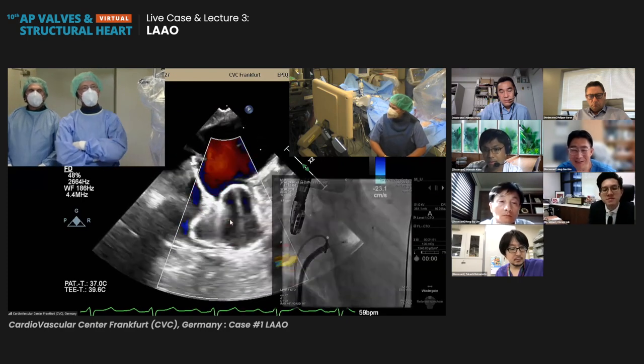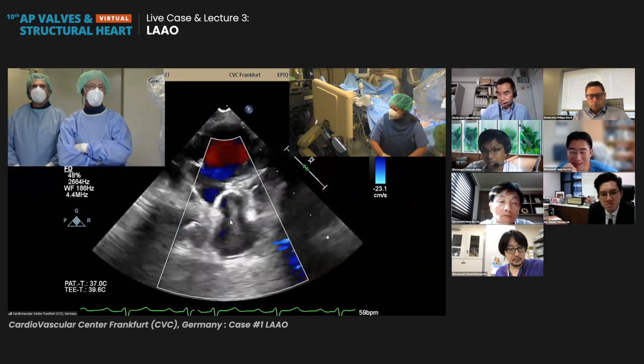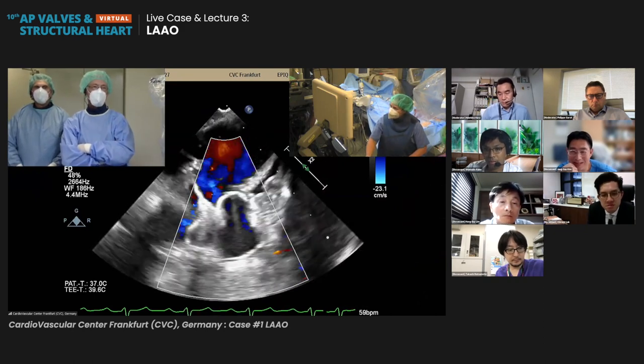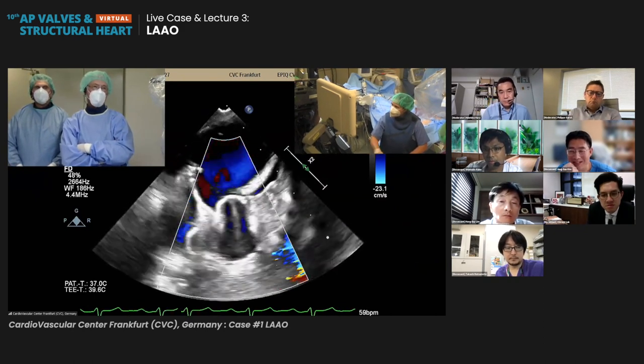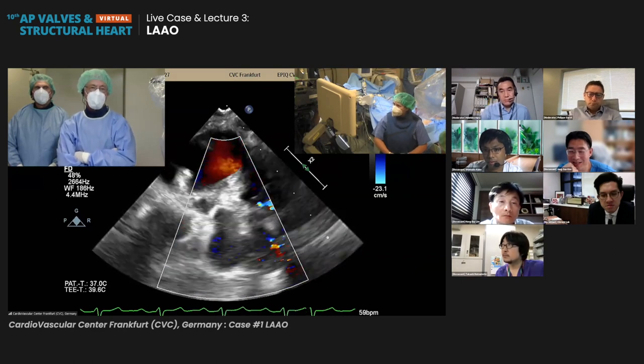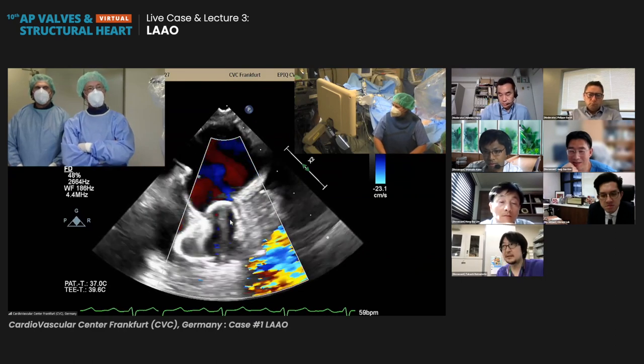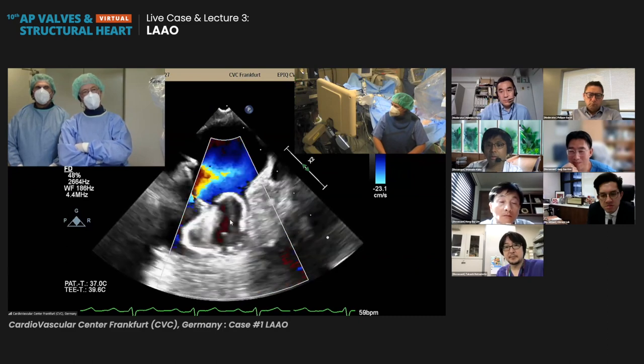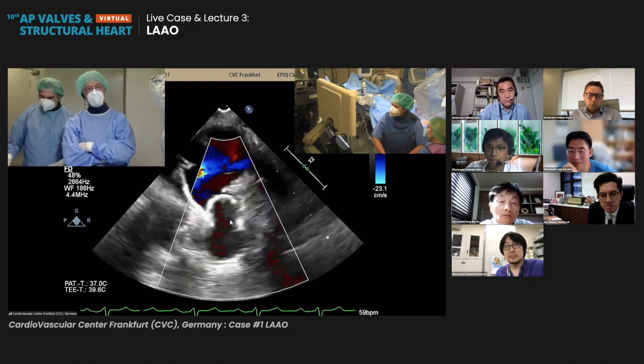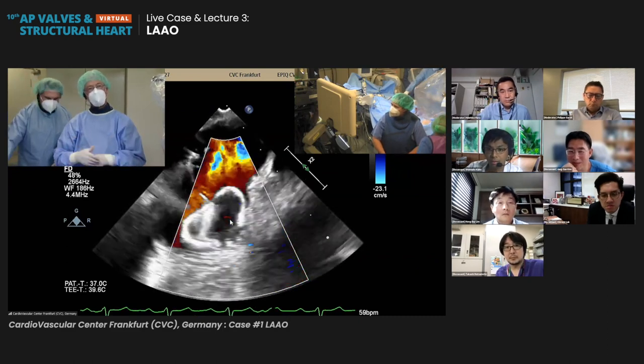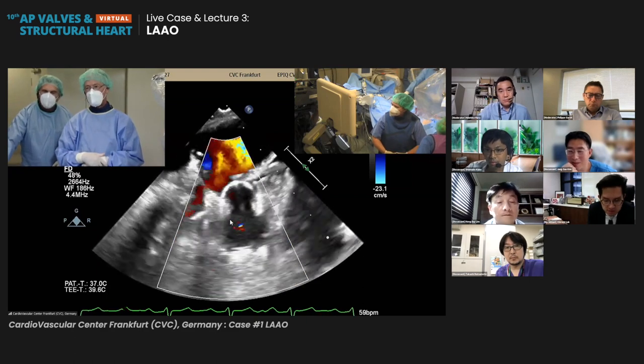Well, according to the literature and the generally accepted rules, this is not a residual leak. Yeah, that's right, I agree. Because if this is called a residual leak, then all Amulet and all Watchman devices would have a residual leak. So a leak is defined by flow going distal to the device, which is not the case here.